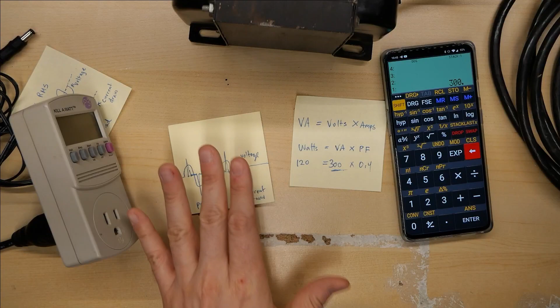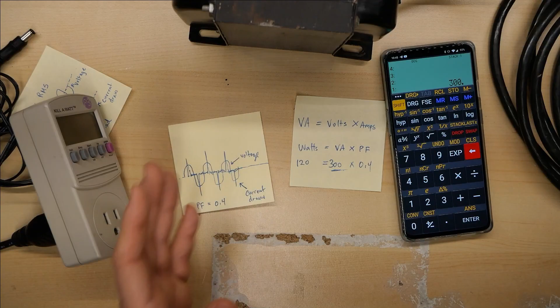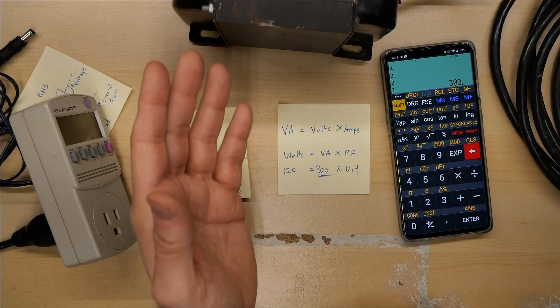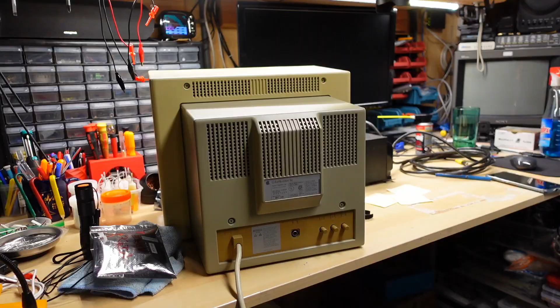But using the power factor even at a lesser load, along with the wattage listed on the label of the power supply, you can make a rough calculation like we did here to make sure you're not going to exceed the maximum capacity of the isolation transformer or the UPS.